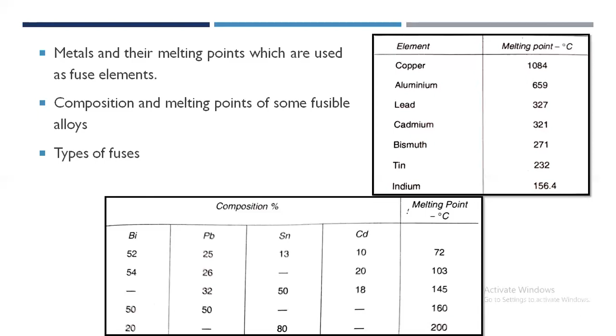High voltage is the HRC cartridge type of fuse. Similar in construction, as low voltage designs, they are used up to 33 kilovolt. High voltage HRC liquid type fuses have the widest range of application to high voltage systems. They may be used for voltage transformer protection or for circuits up to about 400 ampere rated current on systems up to 132 kilovolt or higher. The liquid which surrounds the fuse elements helps to extinguish the arc when the fuse blows.